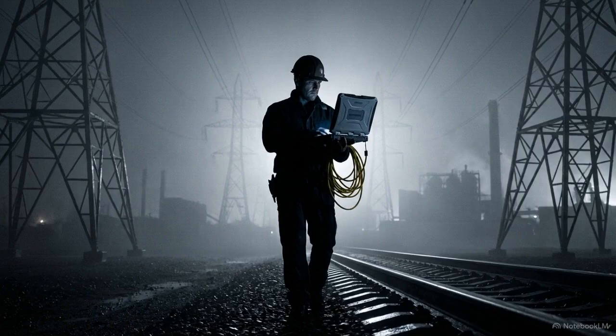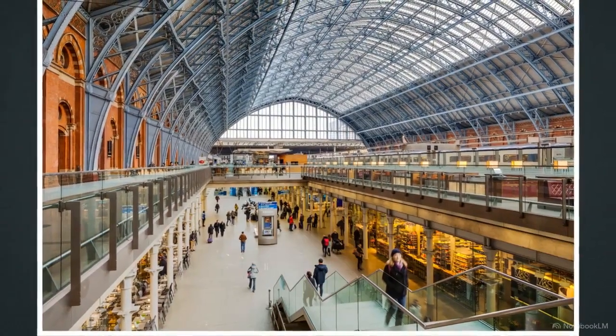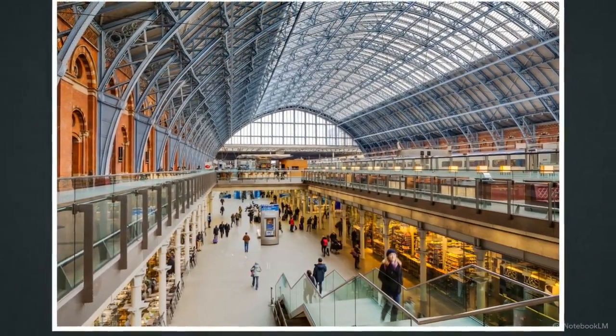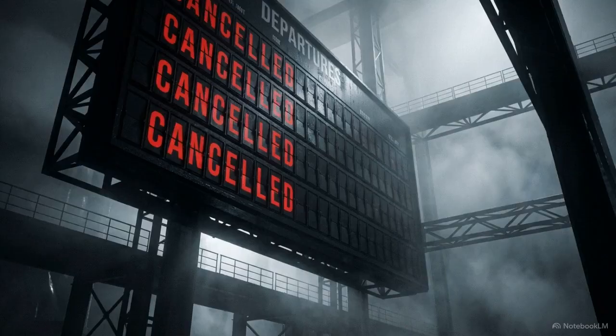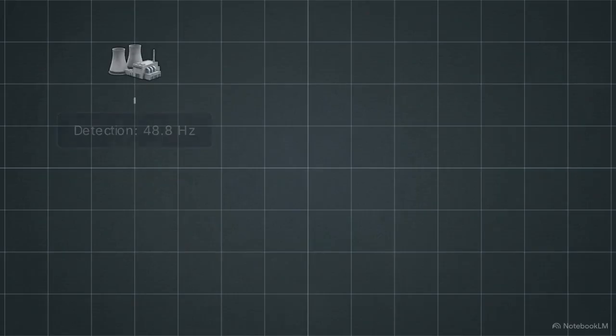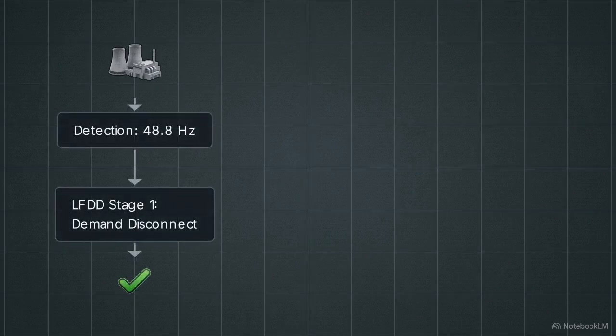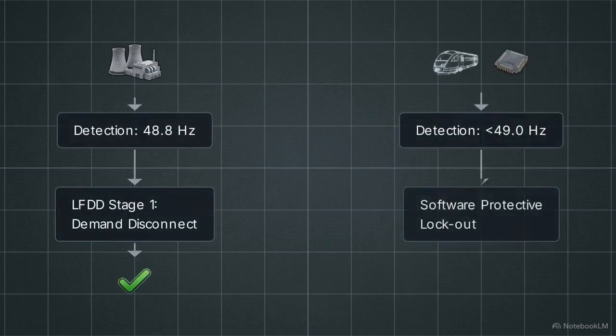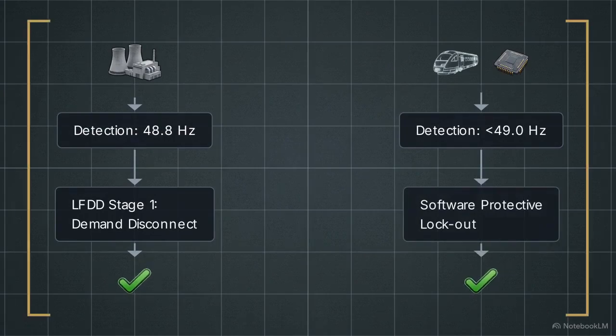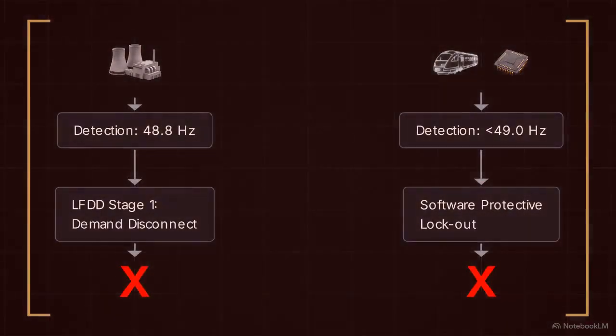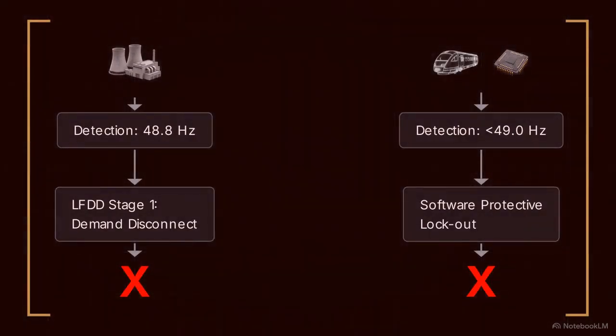Recovery required dispatching technicians on foot with laptops to manually reset the software on each individual train, forcing the cancellation of hundreds of services. With tracks blocked and schedules ruined, massive crowds backed up at major transport hubs like St. Pancras International. Passengers faced severe delays that rippled into the following days, entirely due to isolated software protocols. The grid's automated systems succeeded by shutting power down to protect the network. The train's automated systems protected their electrical drives by doing the exact same thing. Both systems worked perfectly in isolation, but failed spectacularly in combination.